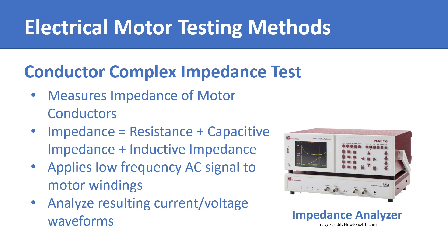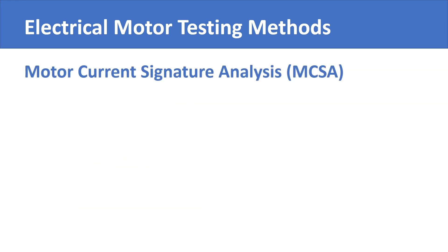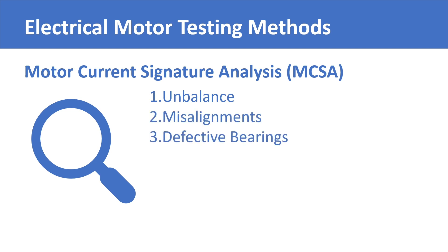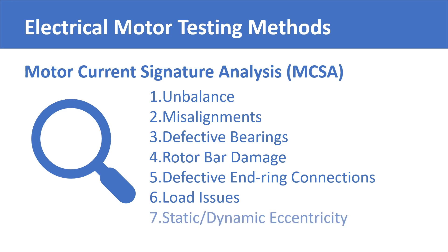Motor current signature analysis, or MCSA, is another sophisticated test for electric motors. It finds unbalance, misalignment, defective bearings, rotor bar damage, defective end-ring connections, load issues, and static or dynamic eccentricity in electric motors.